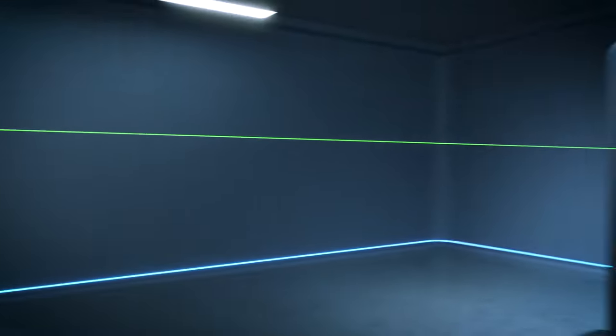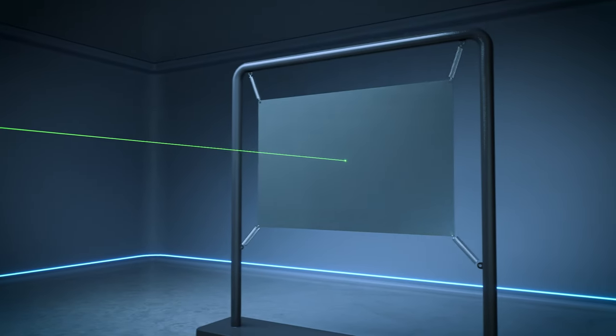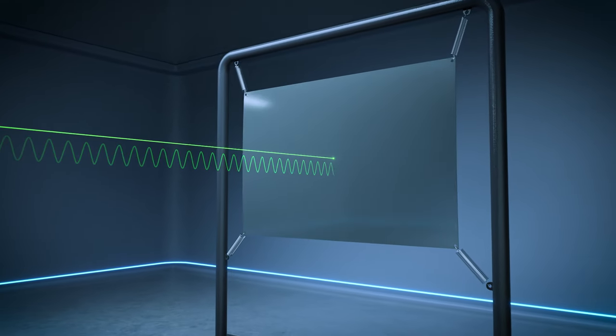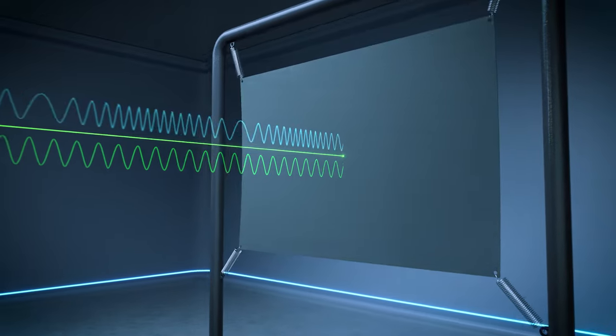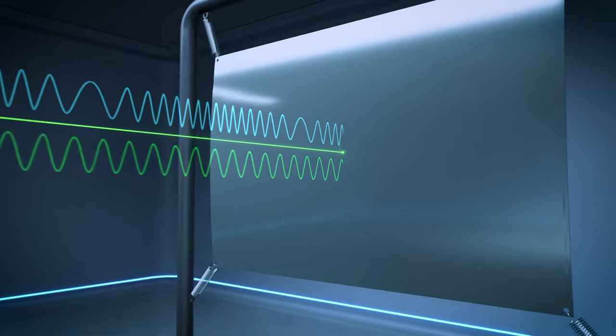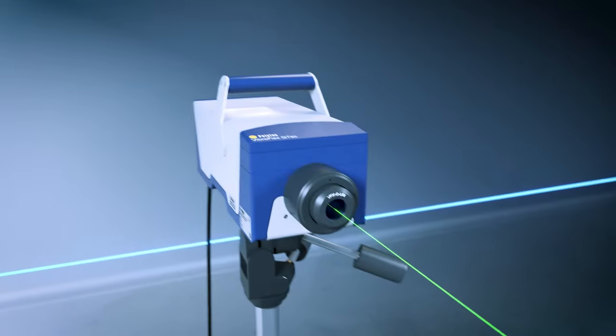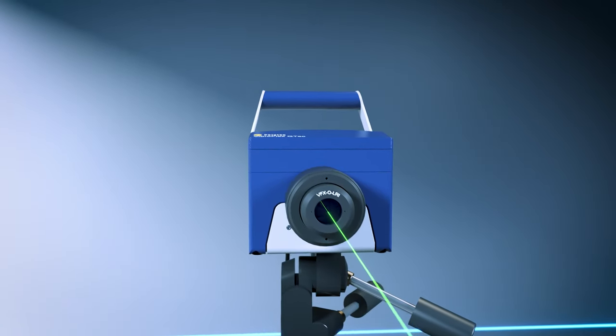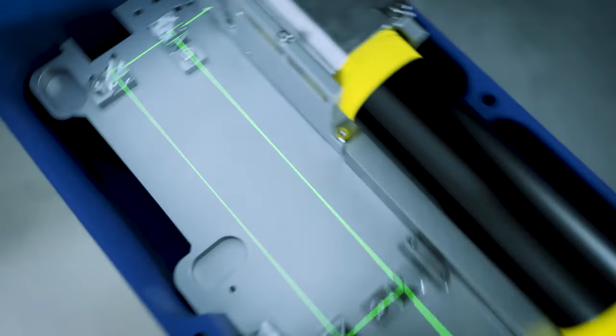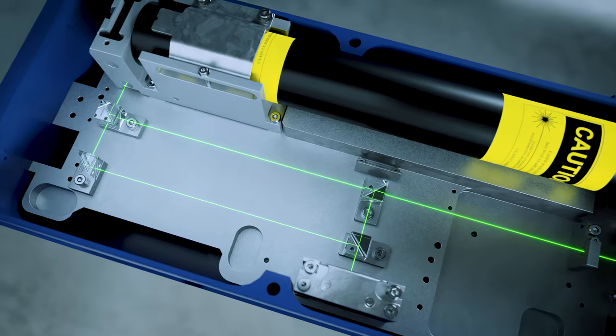Laser vibrometry uses the Doppler effect to measure vibrations. If light is scattered from a moving object, its frequency is changed slightly. Within a Polytec vibrometer, a high-precision interferometer detects the minute frequency shifts of the backscattered laser light.